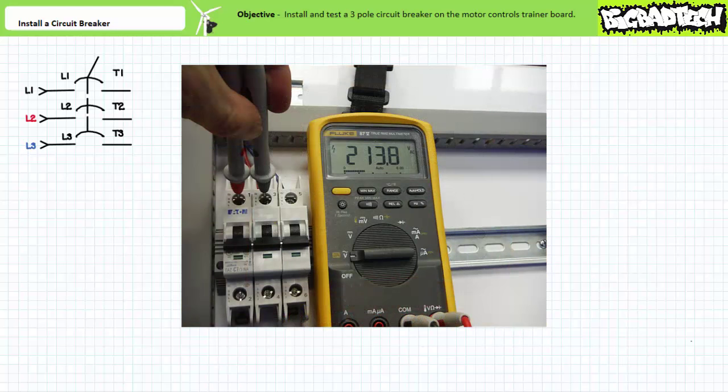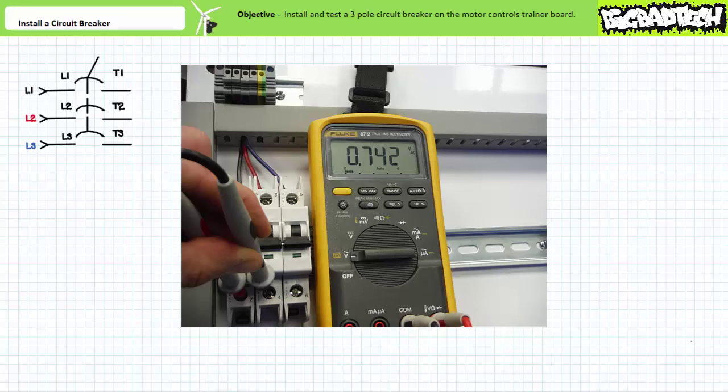When the plug is unlocked and inserted note the DMM indicates the top of the open circuit breaker is hot as expected. The DMM indicates the bottom of the open circuit breaker is cold as expected.